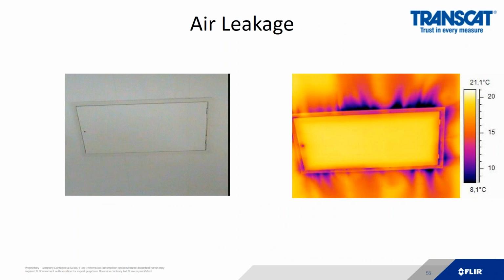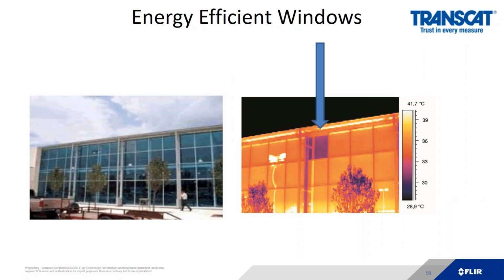If you can create negative pressure within your building, you can see air infiltration and where you need to do additional sealing and insulation, like we do here on this drop ceiling. People like to use infrared cameras for the energy efficiency of their windows. Windows tend to be a bit of a challenge. They're very reflective. In this case, they put the window in backwards.